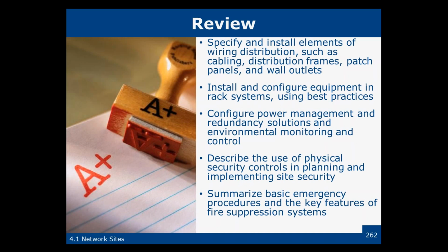You need to install a mixture of 1U servers and switches and 4U servers in a single rack. Would a 4 or a 2-post rack be most suitable? A 4, wouldn't it? Yeah, 4. 4 posts where devices are secured at the front and back would be required to cope with the heavier 4U units and the overall volume of units being installed.